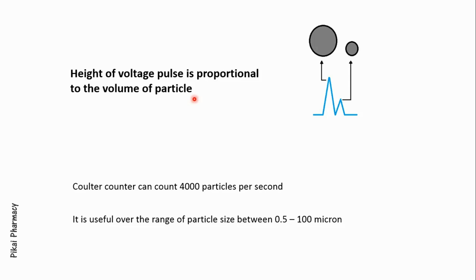In the graphical representation of the voltage pulse, the height of a pulse is proportional to the volume of the particle that enters through the orifice. That means the higher the height of the pulse, the larger is the size of the particle. Each pulse represents a single particle. If your graph contains 30 pulses, then 30 particles were pumped through that orifice.